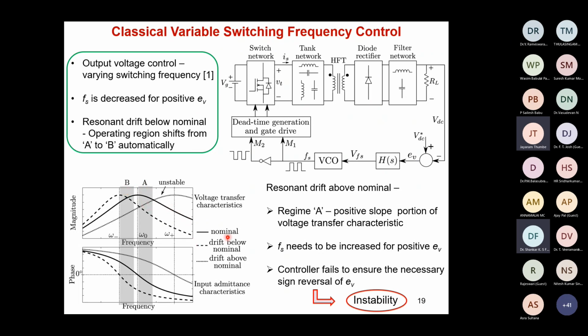But if your tank parameters drift such that your characteristic becomes the small dotted line, then you will fall into the negative slope region of this characteristic. Now what is the problem? If we look at this characteristic on the other slope, for a positive error you should increase switching frequency so that you can again regulate.